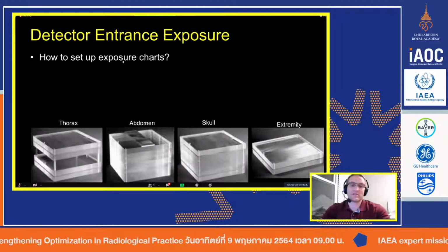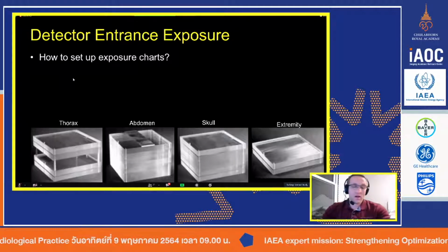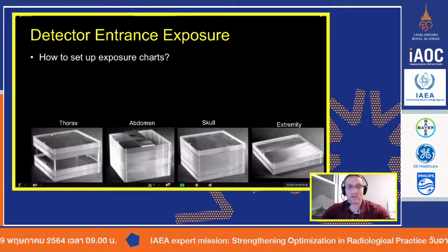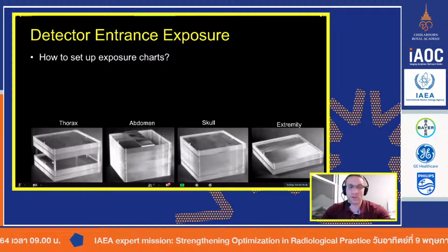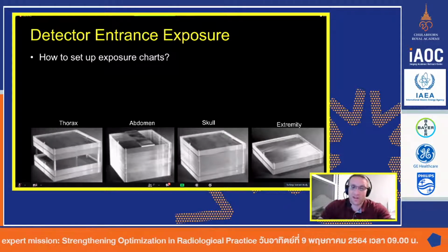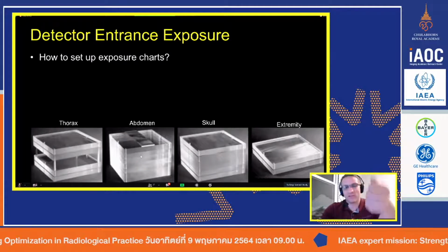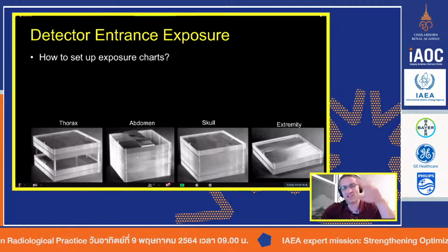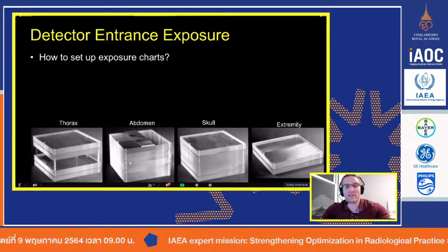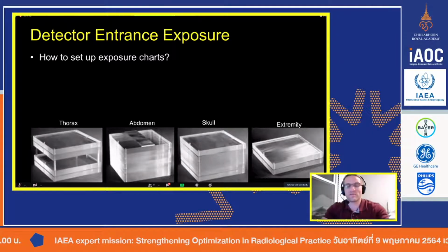So how do you set up these exposure charts, or how do you verify them? Well, we've talked quite a bit about using different types of phantoms. We talked about using plastic, these PMMA blocks. They're great. They're not patients, of course, but they're very adjustable. I can add a block or take away a block. So I can change the overall thickness of my quote unquote patient so I can get a rough idea of how the exposure, the technique factors, will change with size.